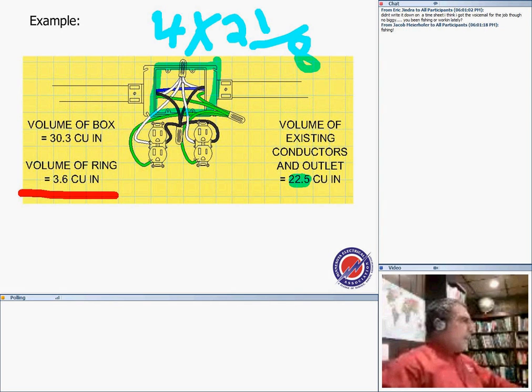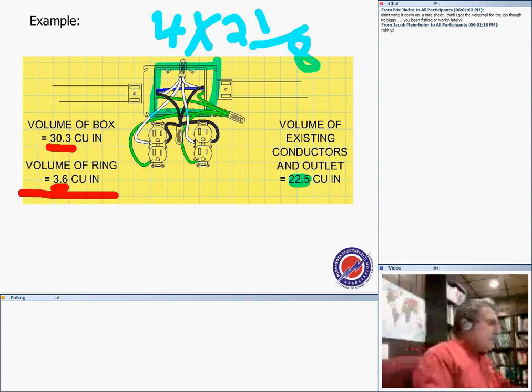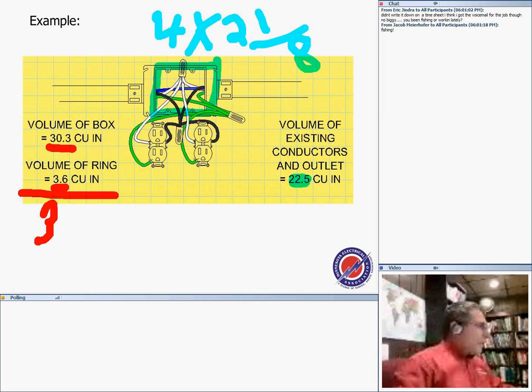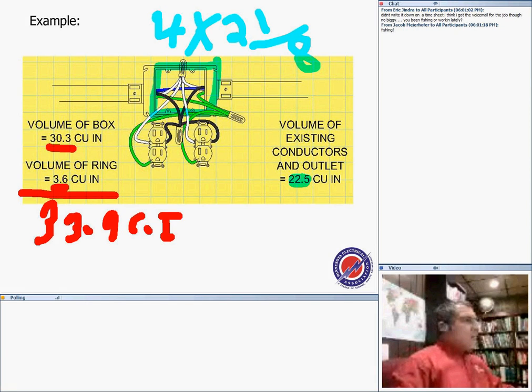So my box is 30.3. I have a mud ring around it, which is 3.6. So add these two together, guys. That's easy to do. That will get me to 33.9 cubic inches. So the question is how many extra conductors can I add to this box? Well, this is how much the box can handle altogether.